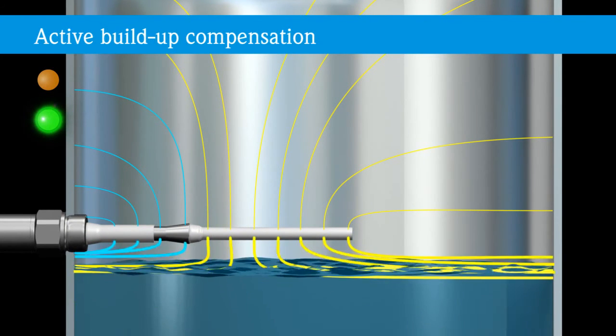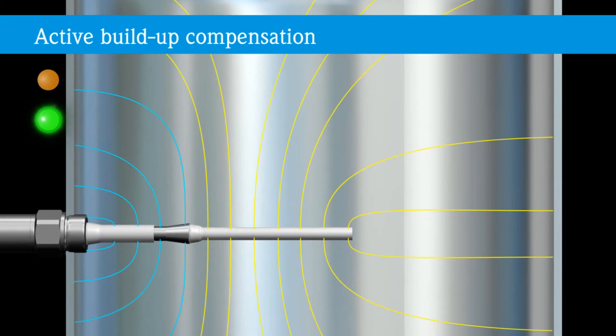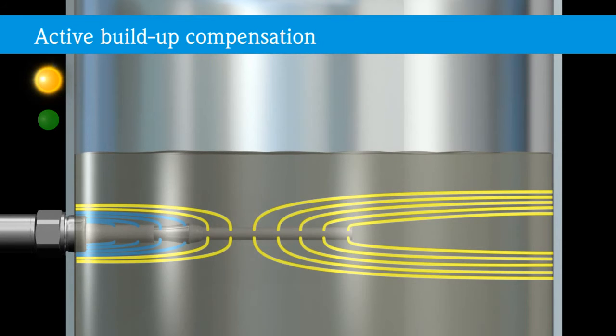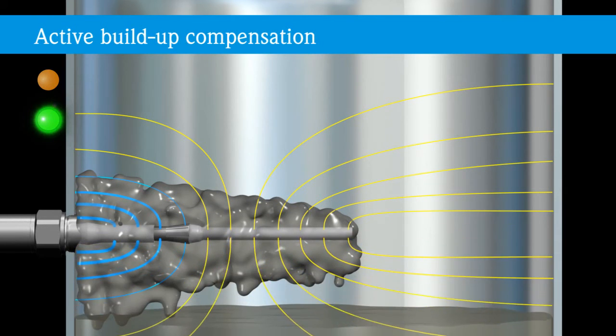The shielding effect of the active build-up compensation prevents a direct current flow along the probe electrode to the tank wall. Therefore, the current of the probe does not flow in the area of the build-up, but only in the area of the actual level. This principle enables the probe to measure reliably even in spite of strong conductive build-up.